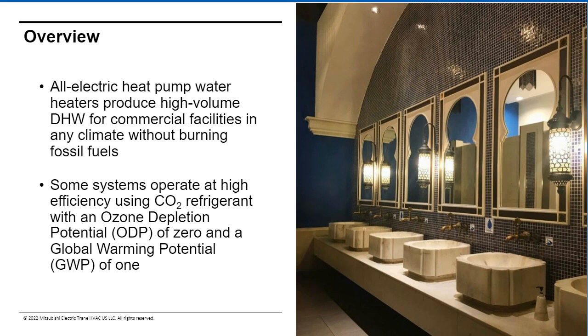So the real overall goal is to get a product or solution out to the market that can remove the need for fossil fuels in a building. And that's really what a lot of those legislation and rules are surrounding. One of the natural benefits of CO2 refrigeration is that we have an ozone depletion potential of 0 and a GWP of 1 for that refrigerant type. So while it's the best refrigerant type for this type of solution, it also adds the natural benefits of being a natural refrigerant and having very little environmental impact to our world here.